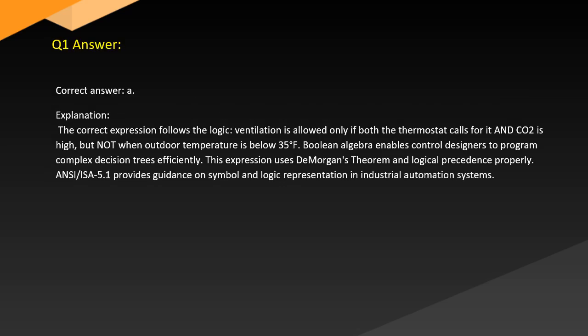Answer. Correct answer A. Explanation. The correct expression follows the logic. Ventilation is allowed only if both the thermostat calls for it and CO2 is high, but not when outdoor temperature is below 35 degrees. Boolean algebra enables control designers to program complex decision trees efficiently. This expression uses De Morgan's theorem and logical precedence properly. ANSI 5.1 provides guidance on symbol and logic representation in industrial automation systems.